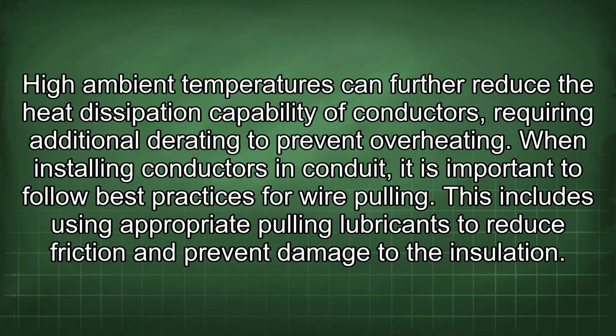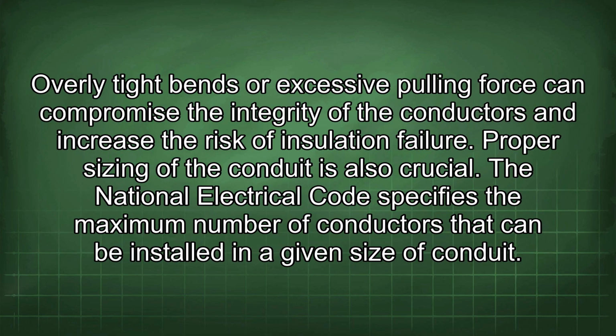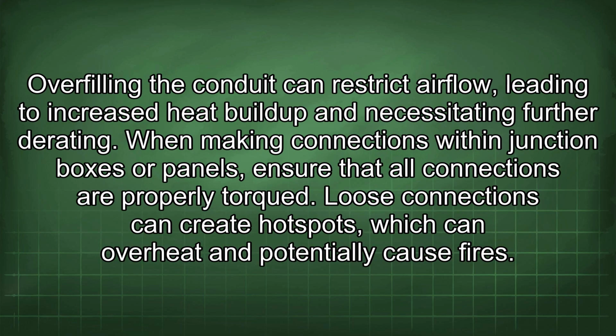When installing conductors in conduit, it is important to follow best practices for wire pulling. This includes using appropriate pulling lubricants to reduce friction and prevent damage to the insulation. Overly tight bends or excessive pulling force can compromise the integrity of the conductors and increase the risk of insulation failure. Proper sizing of the conduit is also crucial. The National Electrical Code specifies the maximum number of conductors that can be installed in a given size of conduit. Overfilling the conduit can restrict airflow, leading to increased heat buildup and necessitating further derating.